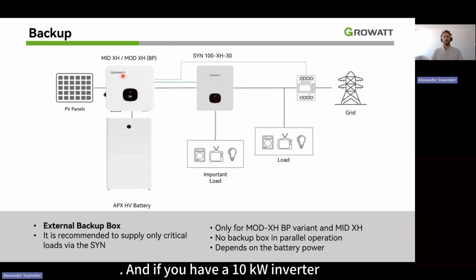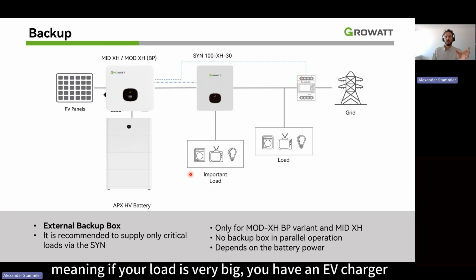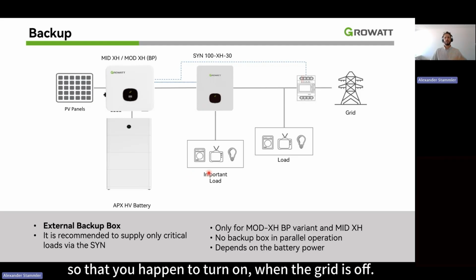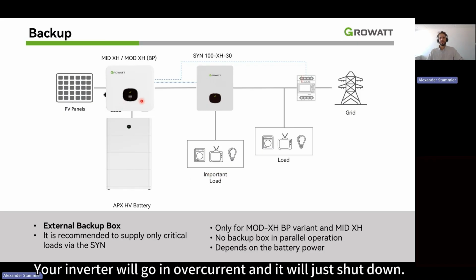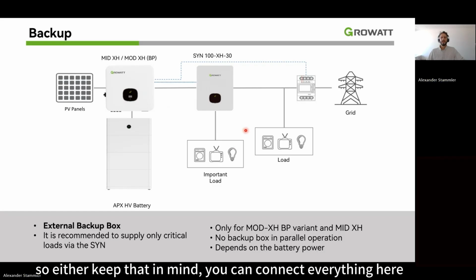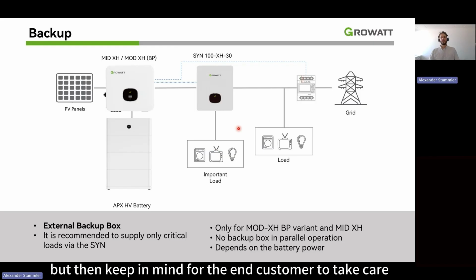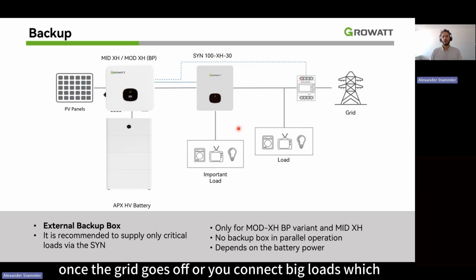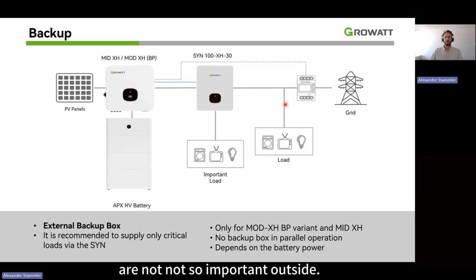And if you have a 10 kilowatt inverter, it will only give you 3 kilowatt per phase. Meaning if your load is very big, you have an EV charger that happens to turn on when the grid is off, your inverter will go in overcurrent and it will just shut down. So keep that in mind. I mean, you can connect everything here, but then keep in mind for the end customer to take care once the grid goes off, or you connect big loads which are not so important outside.